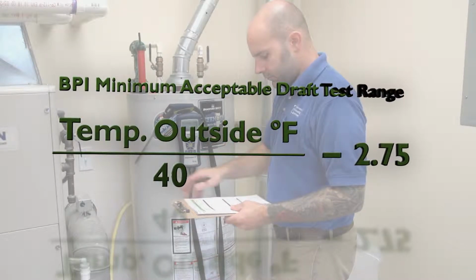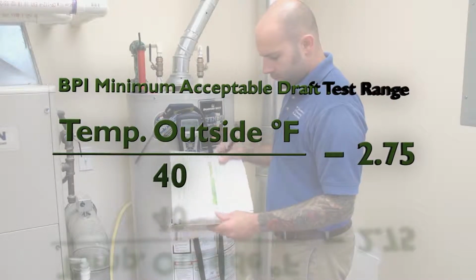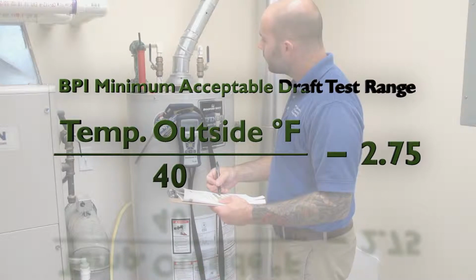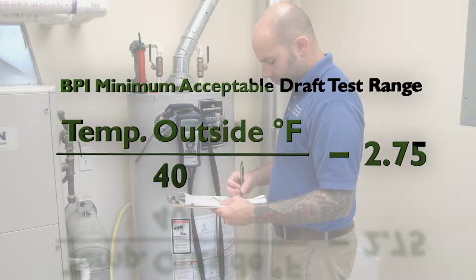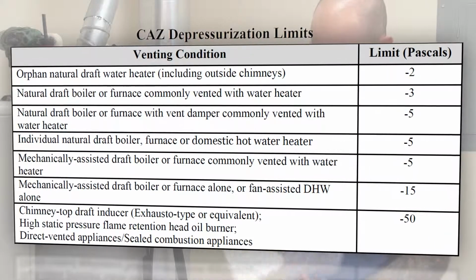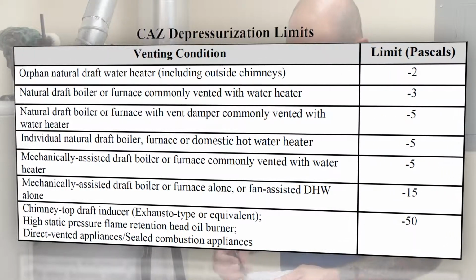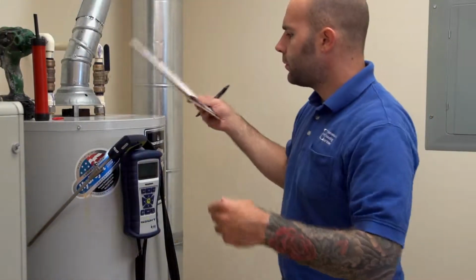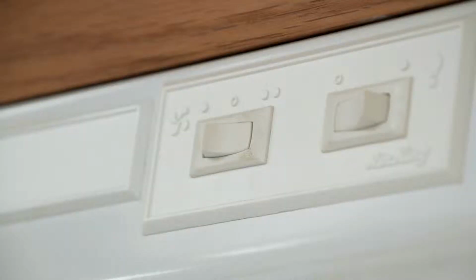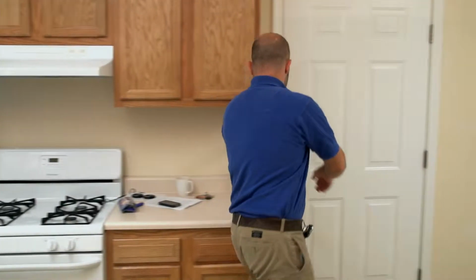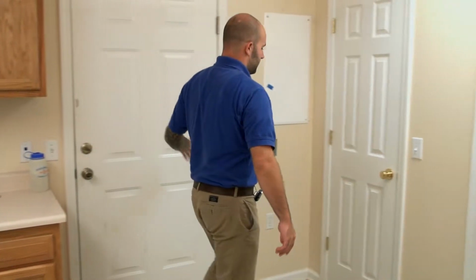Calculate the minimum acceptable draft test range using the BPI method or reference local codes or program standards for tolerable limits. Consult the reference sheet for CAZ depressurization limits. Set up the home for natural or winter conditions. All exterior doors and windows are closed. All interior doors are open, including the door to the CAZ.